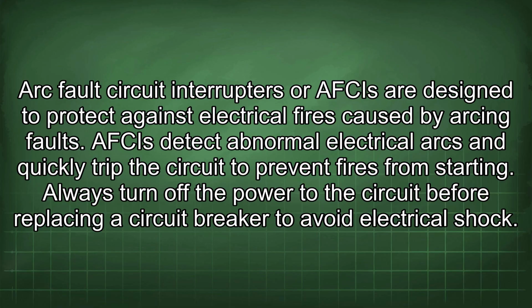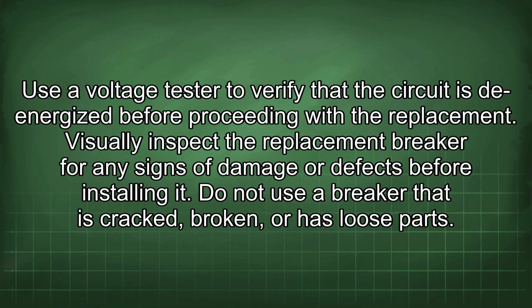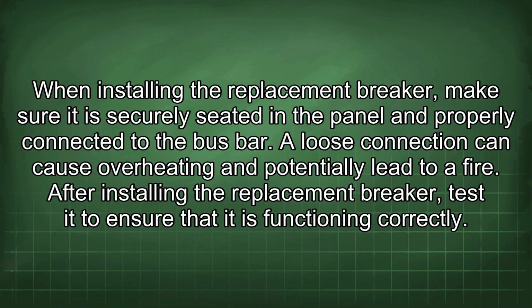Always turn off the power to the circuit before replacing a circuit breaker to avoid electrical shock. Use a voltage tester to verify that the circuit is de-energized before proceeding with the replacement. Visually inspect the replacement breaker for any signs of damage or defects before installing it. Do not use a breaker that is cracked, broken, or has loose parts. When installing the replacement breaker, make sure it is securely seated in the panel and properly connected to the bus bar. A loose connection can cause overheating and potentially lead to a fire.